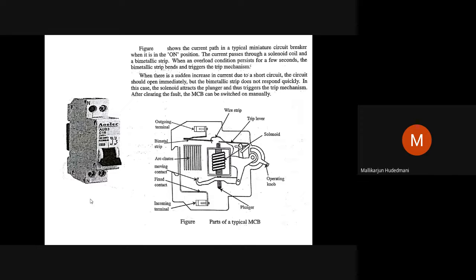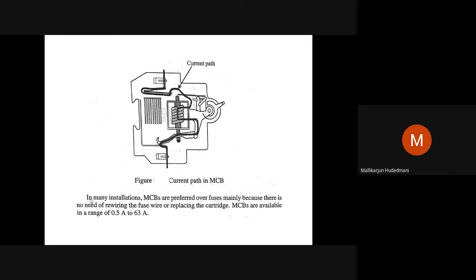How is that internally? Internally, it has a structure like this, which I'll show you as a simple outline. You may need to sketch it. A question could be to sketch the MCB, miniature circuit breaker, and explain it, or compare the fuse with the MCB. For that, one side view is shown to you. There is an incoming current wire. Then there is a flexible wire, and current flows through a coil, an inductive coil. We call it a solenoid. Then it comes to a bimetallic strip. Then it comes to the end lead.